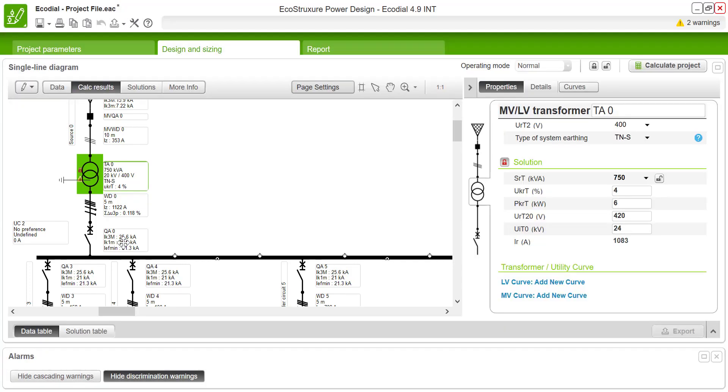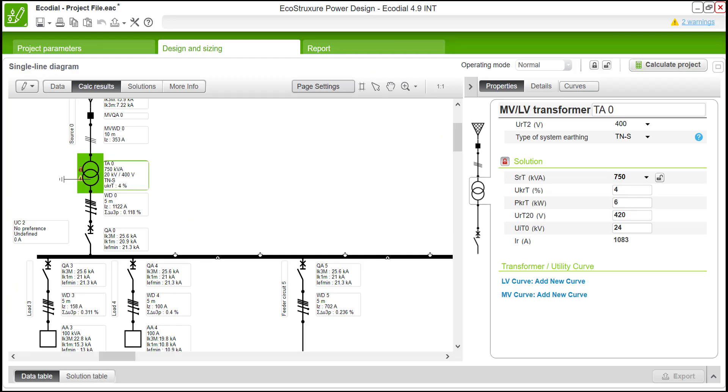You can see there is a change in the short circuit currents after the transformer. Before changing the value, the short circuit current is 16.08 kA, whereas after the transformer characteristics are changed, the short circuit current value is optimized accordingly. Thanks for watching the video. Have a good day and bye-bye.